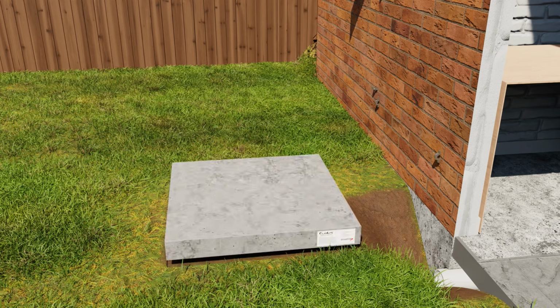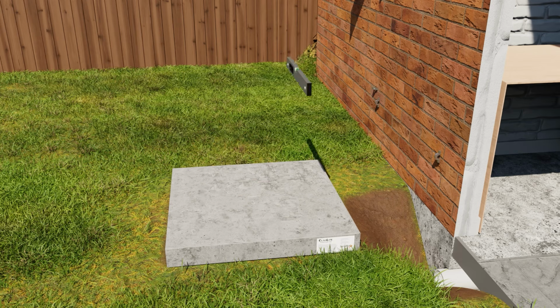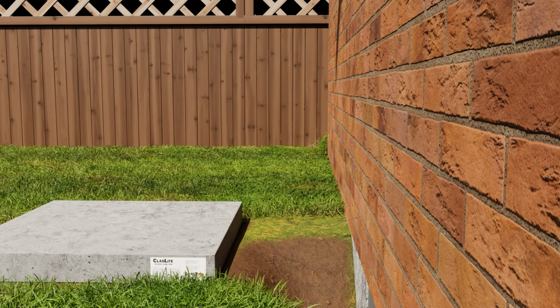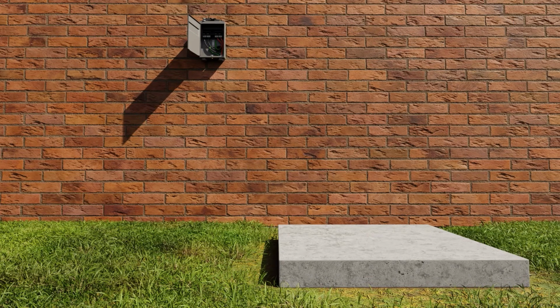Next, install the pad and check the level once again. In general, it's a good best practice to have about 2 feet of clearance from the condenser to the wall and about 1 foot in all other directions. But that can vary based on manufacturer specs and application. You'll also want at least 2 feet of clearance between your dryer vent and your disconnect and the edge of the condenser. That gives you proper service access to your disconnect and ensures that you're not going to pull in a bunch of lint from your dryer vent.